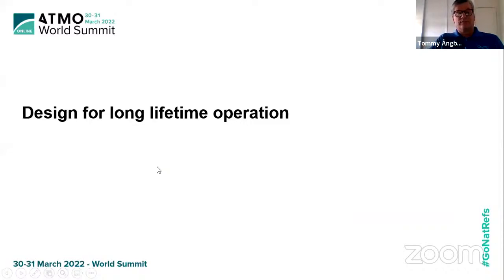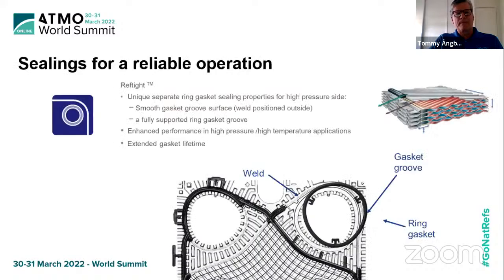Then you have the product installed. That's not the end of it, because we need to be sure that we have long lifetime operation and efficiency over time. And one important thing is the semi-welded plate exchangers, which are a very reliable technology using welded cassettes, plates that are sealed with weld on the higher pressure side, typically the ammonia side, and with gaskets on the open, water side. And that means that you have a lot of advantages. You can take up any variations of temperature and pressures, because there is flexibility in this construction. But it's also possible to open and clean if you have need for that.